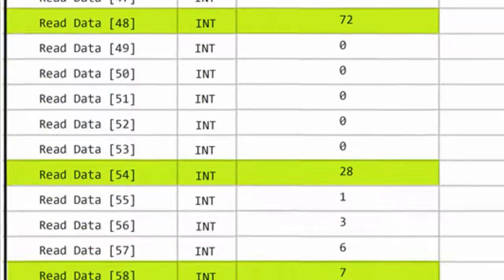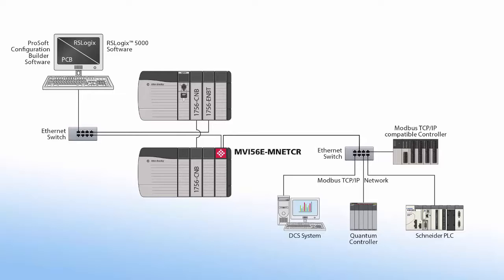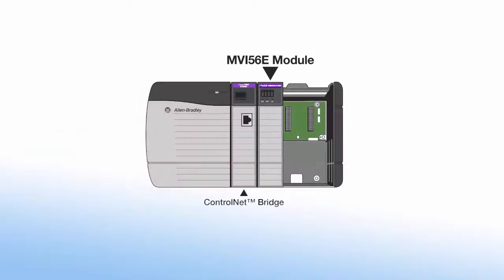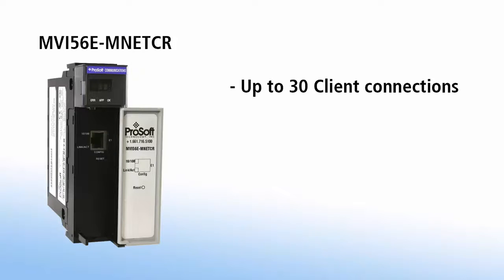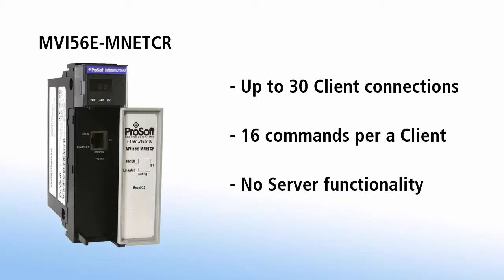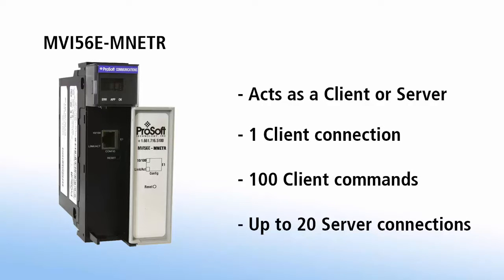Then we have the MVI56E MNET-R and MNET-CR for remote ControlNet rack applications. ControlNet has limitations to how much data you can send in one packet, and these modules are optimized for that issue. The MNET-CR supports 30 client connections with 16 commands each, but has no server functionality. The MNET-R can act as a client and a server, and has functionality similar to the MNET in all other respects.